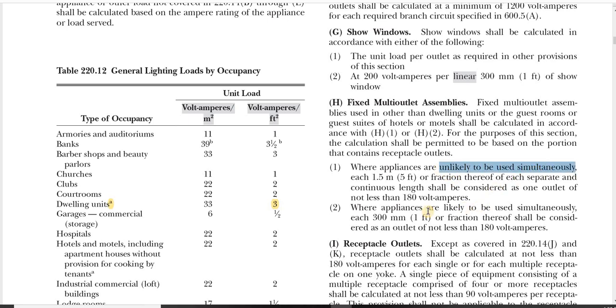All right, now first thing, let's remember a couple things. Even in this 50-foot piece, or even this 65-foot piece, I could have any number of receptacles on there, okay? This is a calculation. Don't confuse it with me having to have one receptacle every foot in the ones that are likely to be used. This is just a calculation for you to be able to calculate the actual VA when you're doing a load calc. So don't consider this as telling me how many receptacles I have to have. This is simply for load calculations, okay?